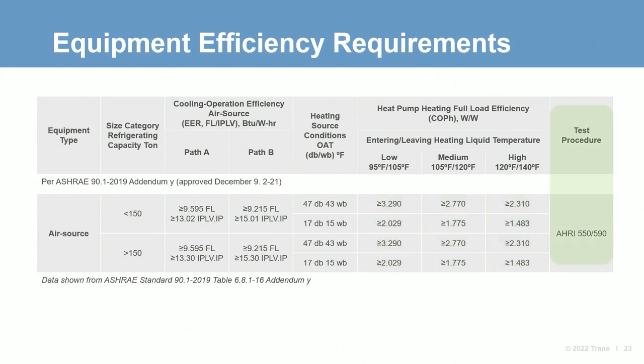Similar to cooling chillers, AHRI 550-590 defines the procedure for verifying unit performance via testing. With unit minimum performance requirements understood, we can review the system code requirements and how they are applicable to chiller heater systems utilizing air-to-water heat pumps. Two common system types seen today are two-pipe and four-pipe. As the name implies, a two-pipe distribution system has one set of supply and return pipes. This system can also be referred to as a two-pipe changeover system.